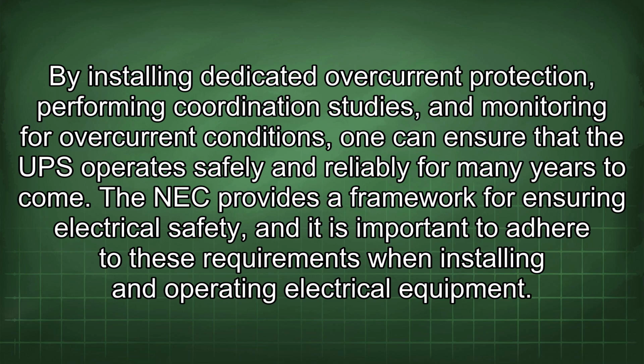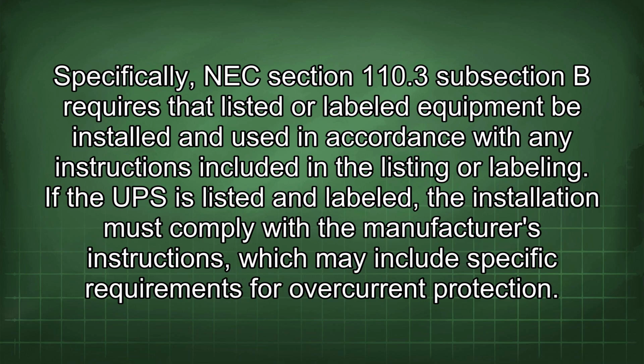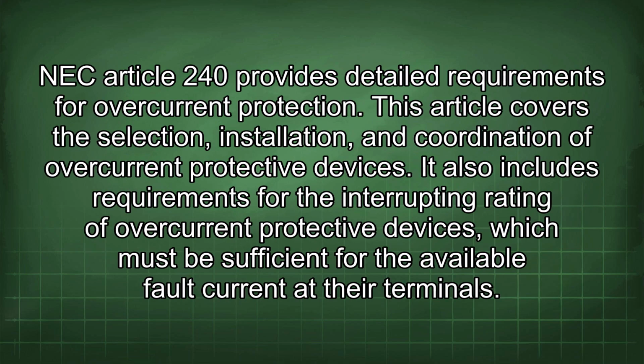The NEC provides a framework for ensuring electrical safety, and it is important to adhere to these requirements when installing and operating electrical equipment. Specifically, NEC Section 110.3(B) requires that listed or labeled equipment be installed and used in accordance with any instructions included in the listing or labeling. If the UPS is listed and labeled, the installation must comply with the manufacturer's instructions, which may include specific requirements for overcurrent protection. NEC Article 240 provides detailed requirements for overcurrent protection.